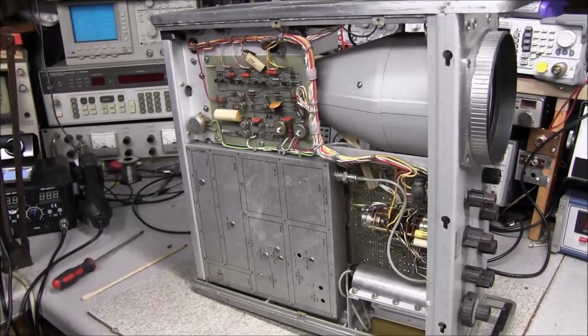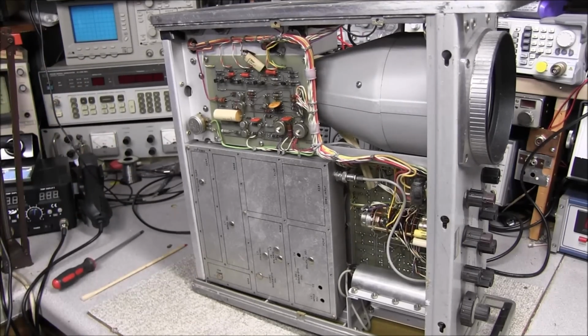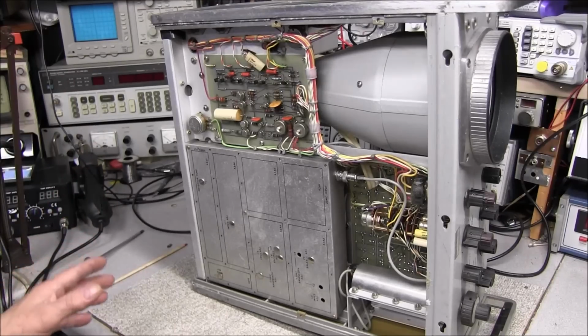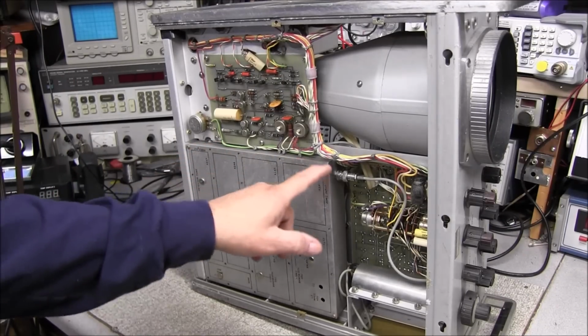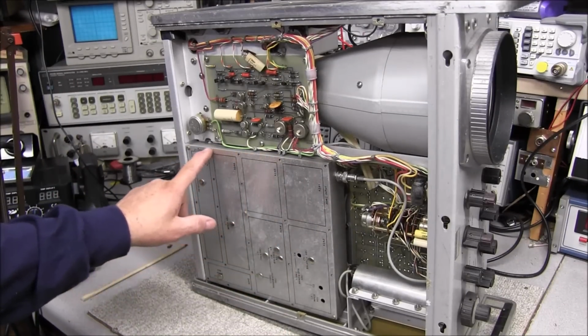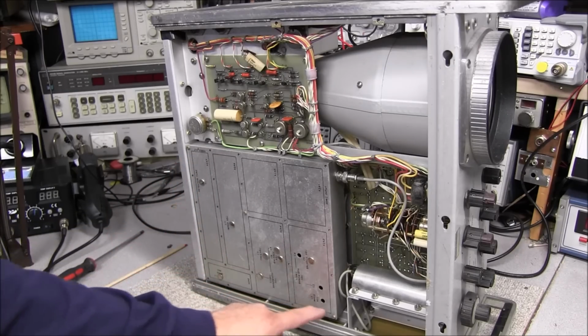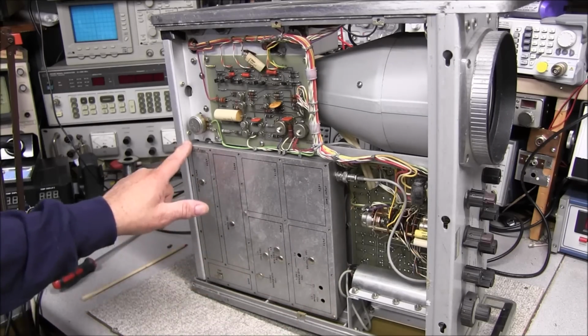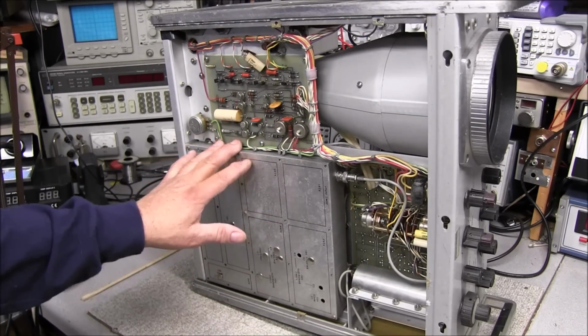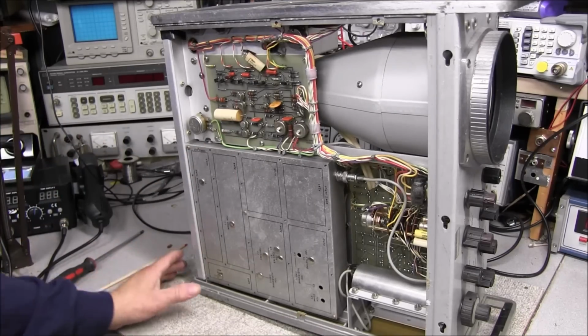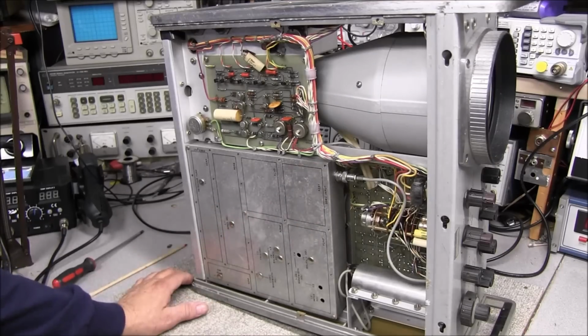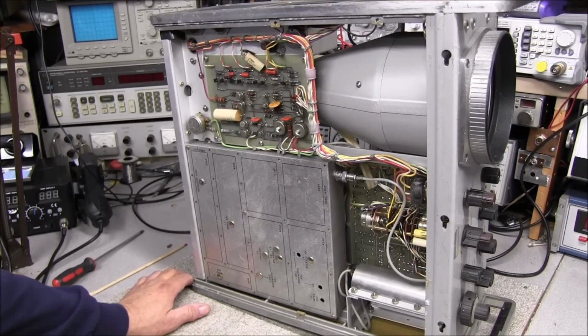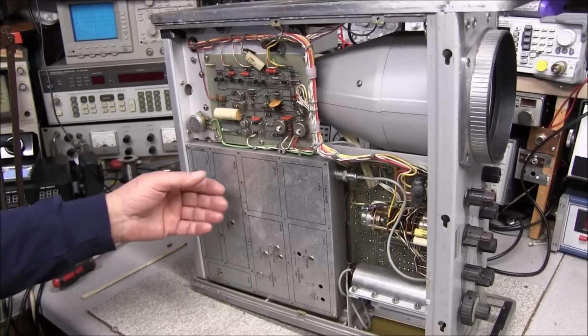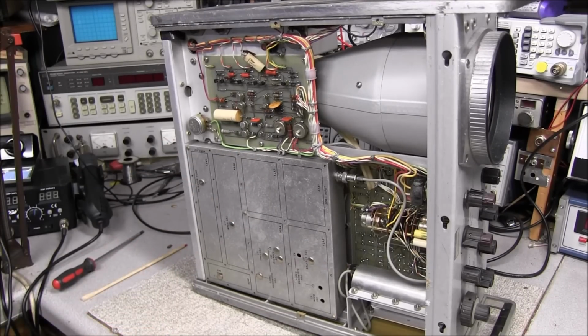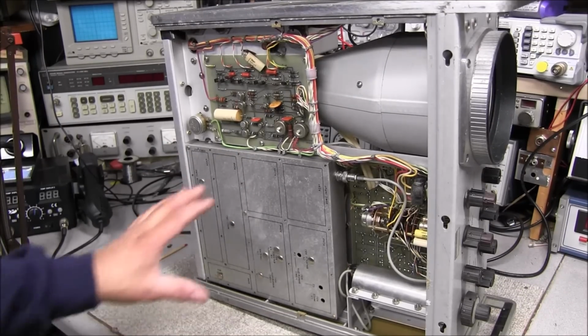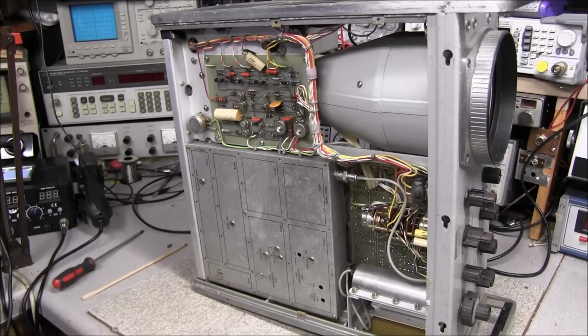Okay, I'll turn the unit over on its side and we remove the bottom cover. First thing that sticks out is on this IF section, all these screws have been removed. There were only 3 screws holding this whole plate on. Now that's another giveaway. That means somebody has been in here working on this IF section or trying to troubleshoot it, and they never did put the screws back in it. So yeah, that's going to be a big concern.